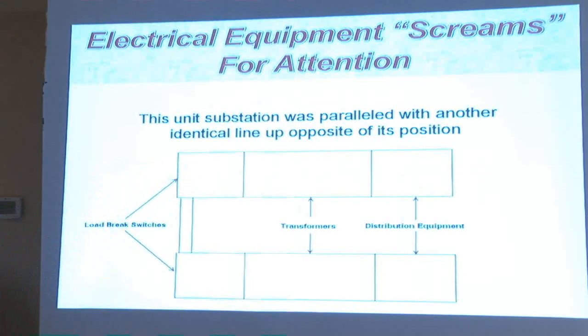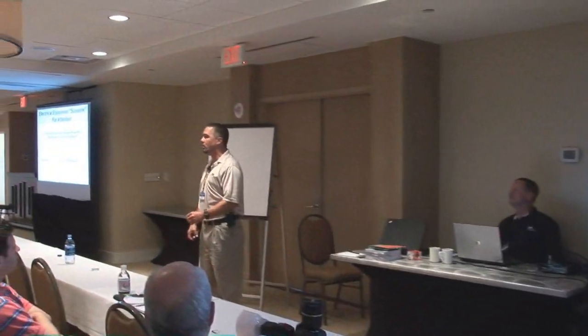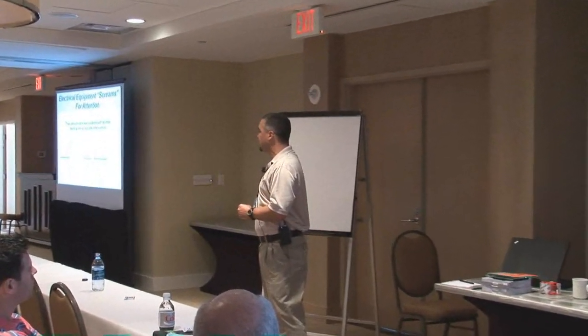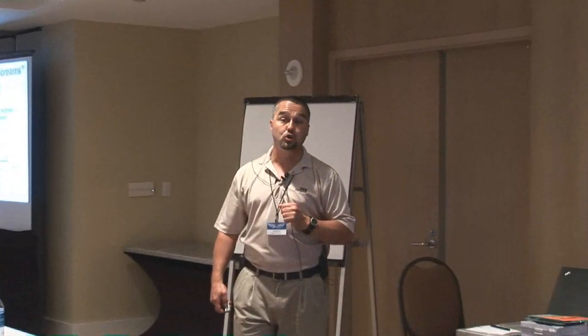This particular lineup was the one we're talking about. Directly opposite of that lineup was one just like it that were tied together. So you can imagine on a 13,000 volt switch, if you have a failure, what I've learned in electrical is failures aren't typically contained to the component that fails. There always seems to be ancillary damage. And certainly the redundancy could have been jeopardized would a failure occur.